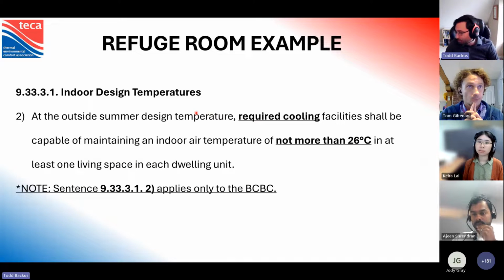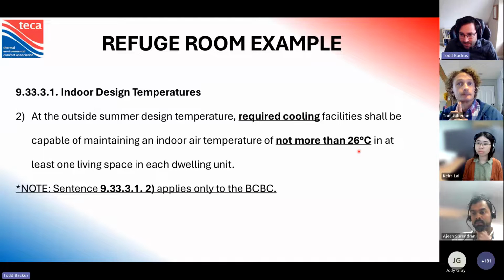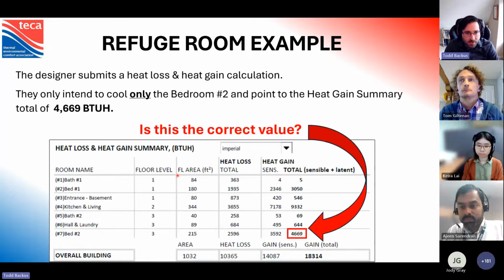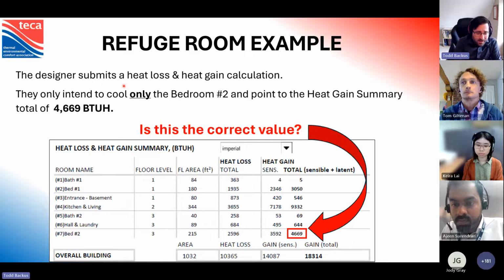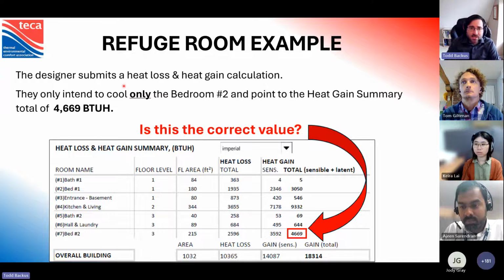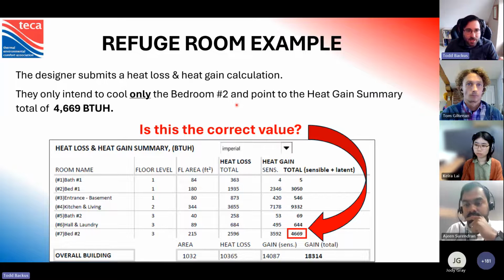So getting on to the refuge room example, required cooling, we have to hit 26 degrees C in at least one living space in each dwelling unit. So this is something that a lot of people are going to run into. They're going to have a designer submit a heat loss, heat gain calculation for the whole house. And they're going to say, okay, I'm only going to cool bedroom number 2. Here is my heat gain summary, and I need 4,669 BTUs for this room. So here we go, bedroom 2, there's that number.